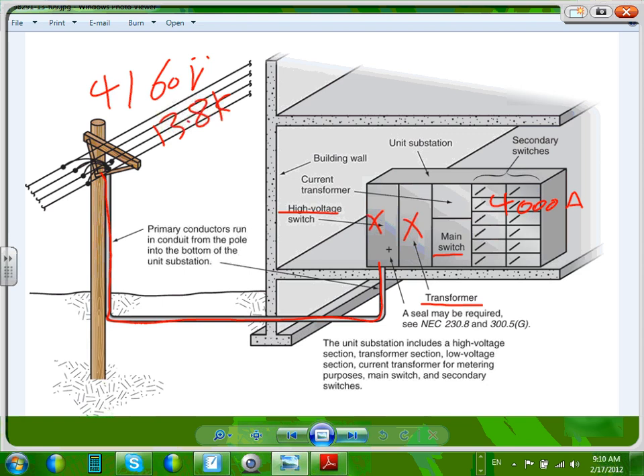The utilities call this the primary feeder. They call it the primary service. You're going to hear them in the industry talking about two types of services, the primary service and secondary service. Most of what you're going to be getting is secondary service, which is secondary conductors, 480, 277, 208, 120. Very large customers like the U of M, 3M, Mayo Clinic, all these big corporations, they get the power at a high voltage level at 13.8.